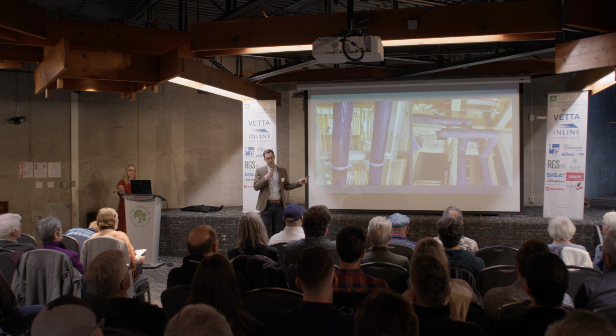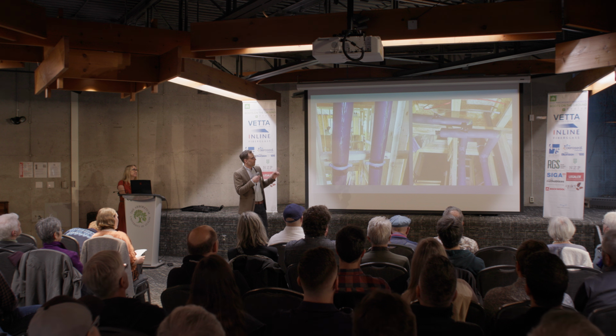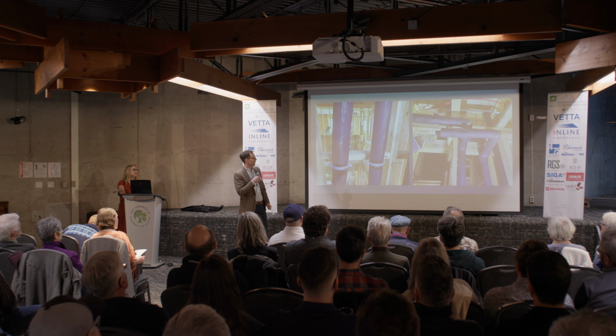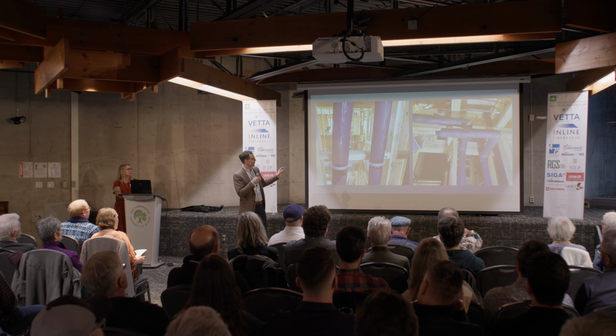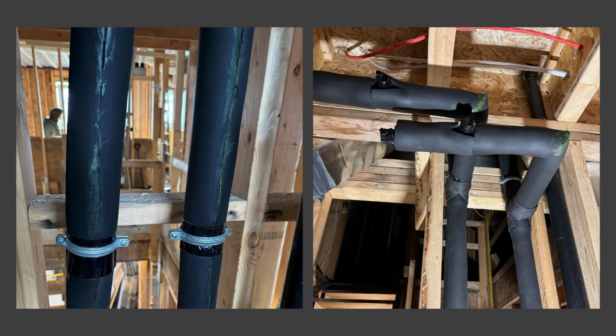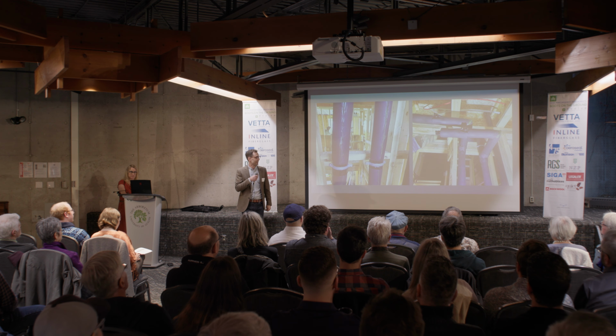And then when we're dealing with chilled water, we need to be really careful compared to dealing with hot water in houses. So this is closed cell elastomeric foam insulation. You can see, if you look closely, the shininess. All of those longitudinal seams have been glued. It's vapor tight. You can see the nice job on mitering the corners too, and gluing that, also vapor tight. And then the contractor wrapped all of those exposure points with tape just to protect them. Cortez Enterprises was the contractor. They did a fantastic job.